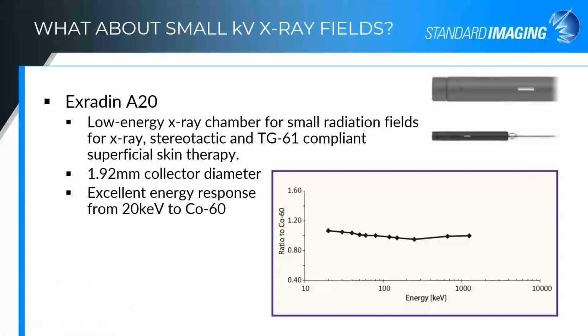We do have a solution as well for small kilovoltage X-ray fields, and that's the Exradin A20. This is actually a parallel plate chamber that is oriented in line with the stem of this chamber. So you would have your field coming from this side, the parallel plates are oriented this way, and then the stem behind it. So this was designed for things like electronic brachytherapy sources, and superficial skin therapy, that sort of thing. It has just under 2 millimeter collector diameter, so it has very good resolution for these small fields as well, and a very excellent low energy response from 20 kV all the way up to cobalt. A very good low energy response.